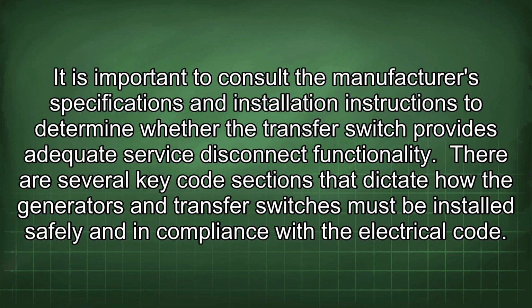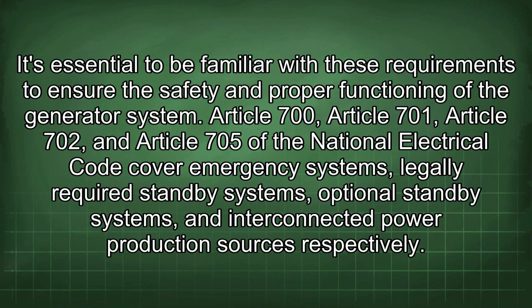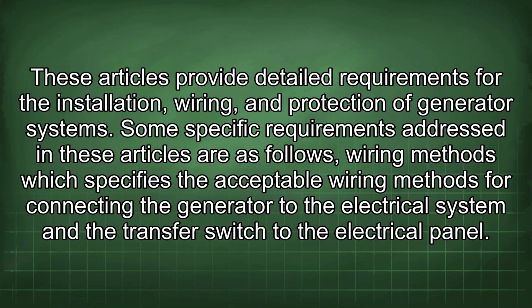There are several key code sections that dictate how generators and transfer switches must be installed safely and in compliance with the electrical code. It's essential to be familiar with these requirements to ensure the safety and proper functioning of the generator system. Article 700, Article 701, Article 702, and Article 705 of the National Electrical Code cover emergency systems, legally required standby systems, optional standby systems, and interconnected power production sources respectively. These articles provide detailed requirements for the installation, wiring, and protection of generator systems. Some specific requirements addressed in these articles are as follows: wiring methods, which specifies the acceptable wiring methods for connecting the generator to the electrical system and the transfer switch to the electrical panel.